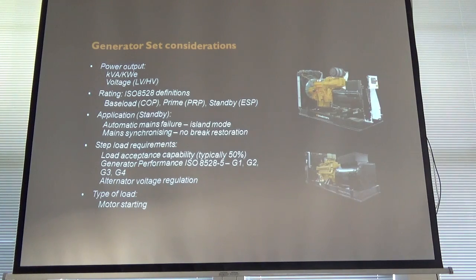Because within each one of the definitions, they go into a lot of detail, and then at the bottom of that, they'll put, unless the manufacturer stipulates otherwise. Well, guess what? He often does. Cummins has a limit of 200 hours per year, and quite a few caveats for their engines. Perkins, or FG Wilson Perkins product, they'll actually warrant that unit for running up to 500 hours per year.